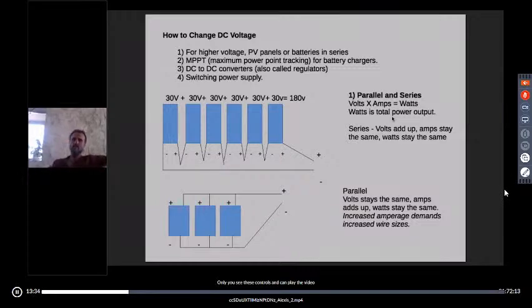So there are four ways to change DC voltage: you can put PV panels or batteries in series or in parallel, which changes the voltage. Something called maximum power point tracking is an electronic device that changes voltage. DC to DC converters, also called regulators, can change DC voltage. And switching power supplies. We'll talk about each one of these in turn.